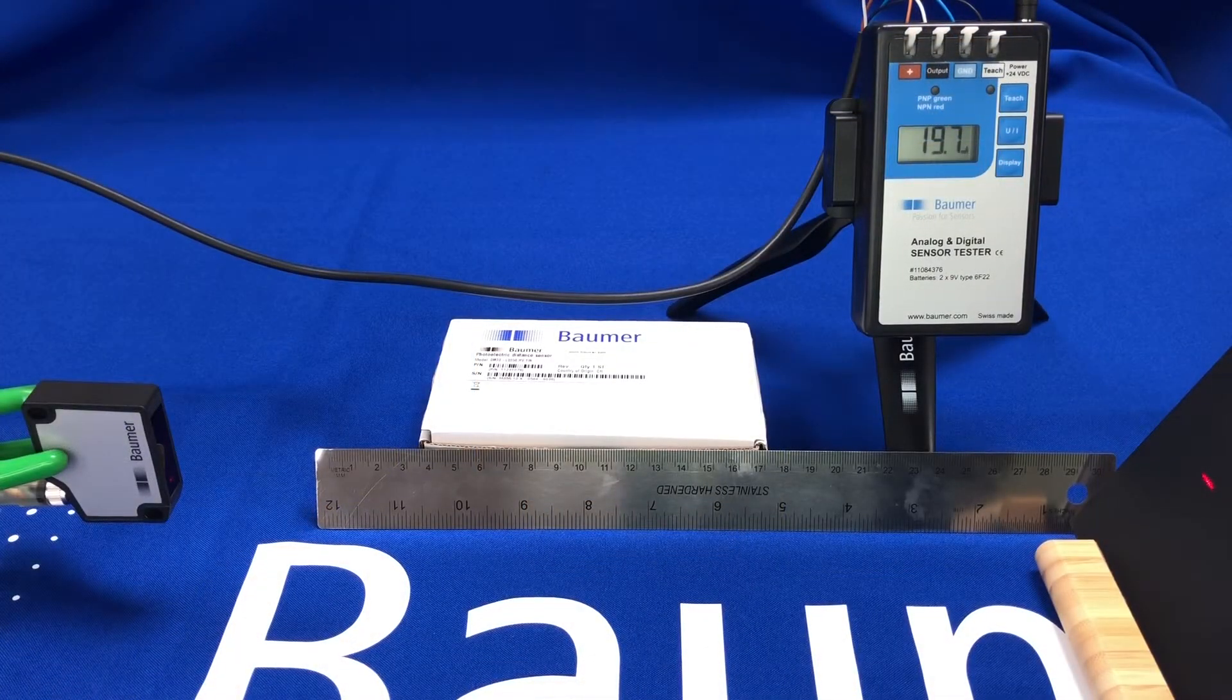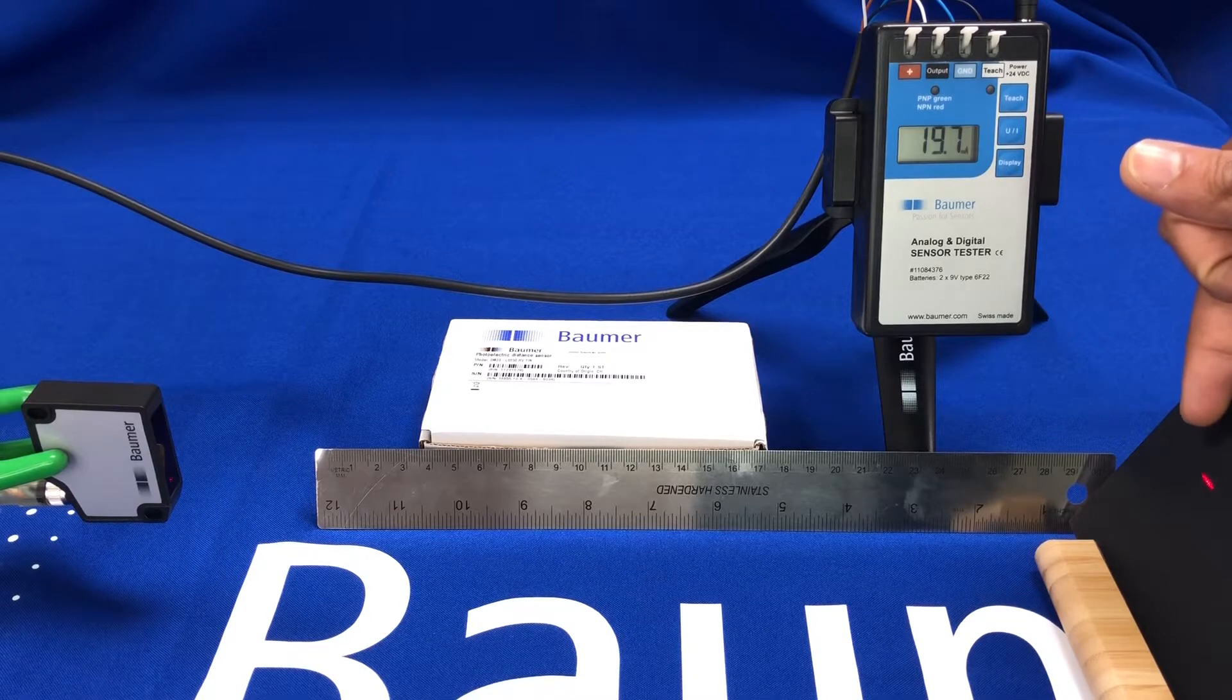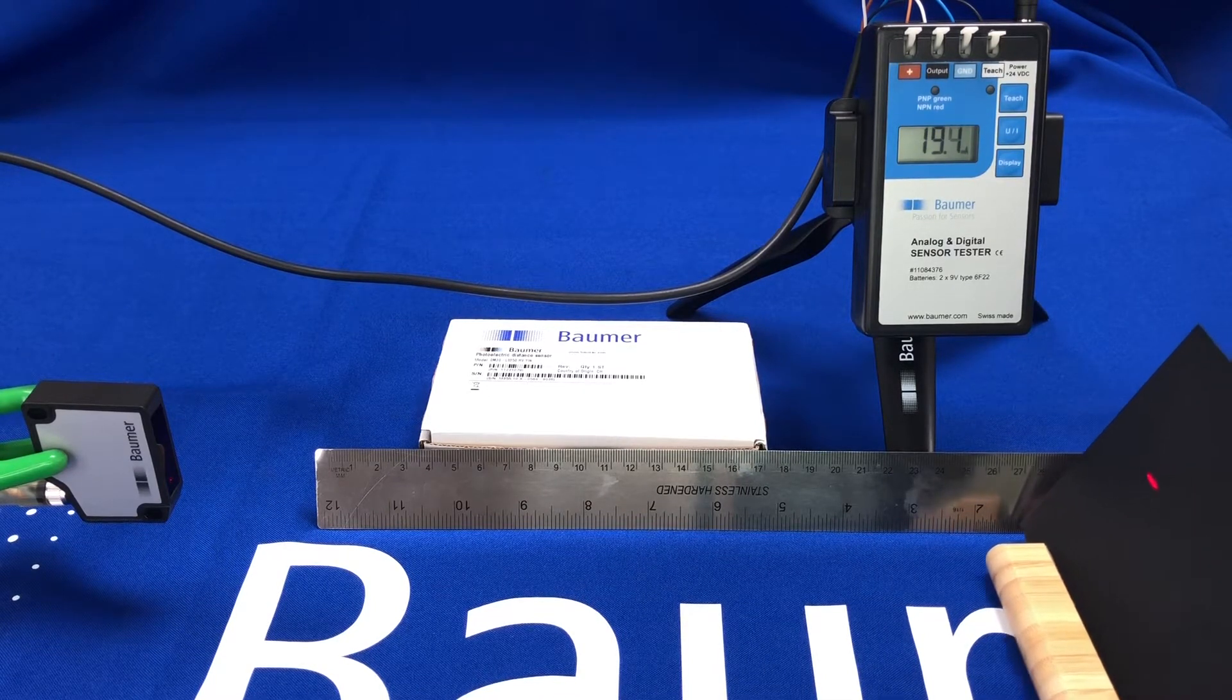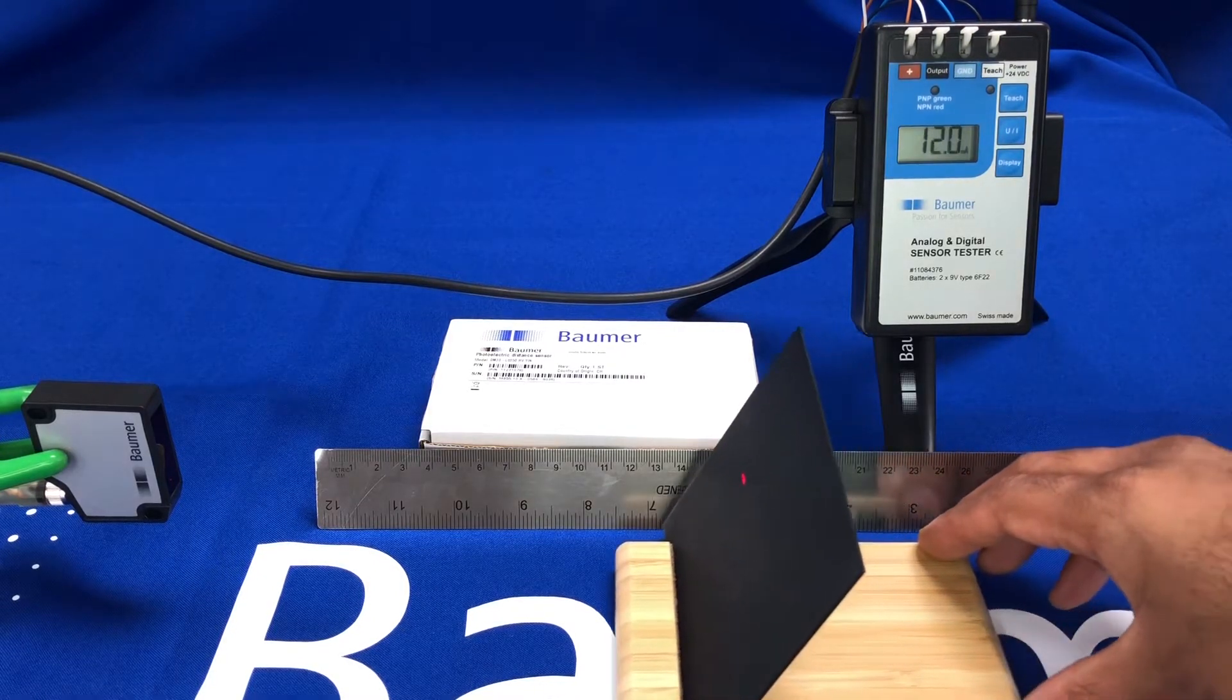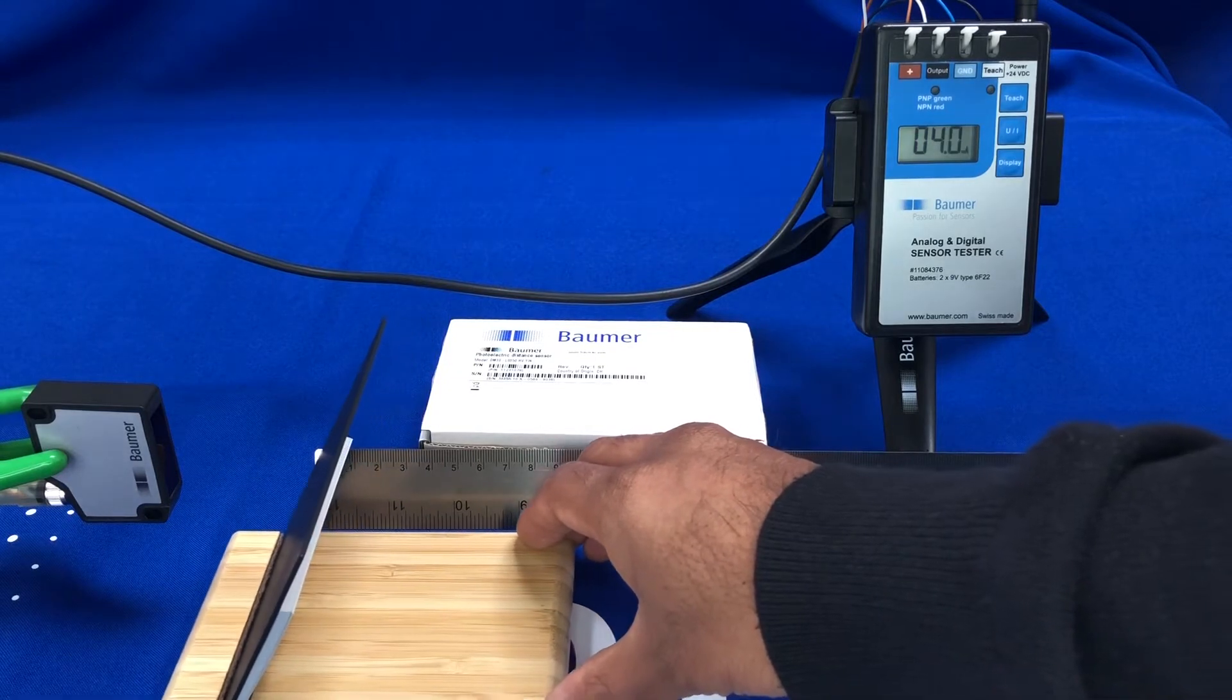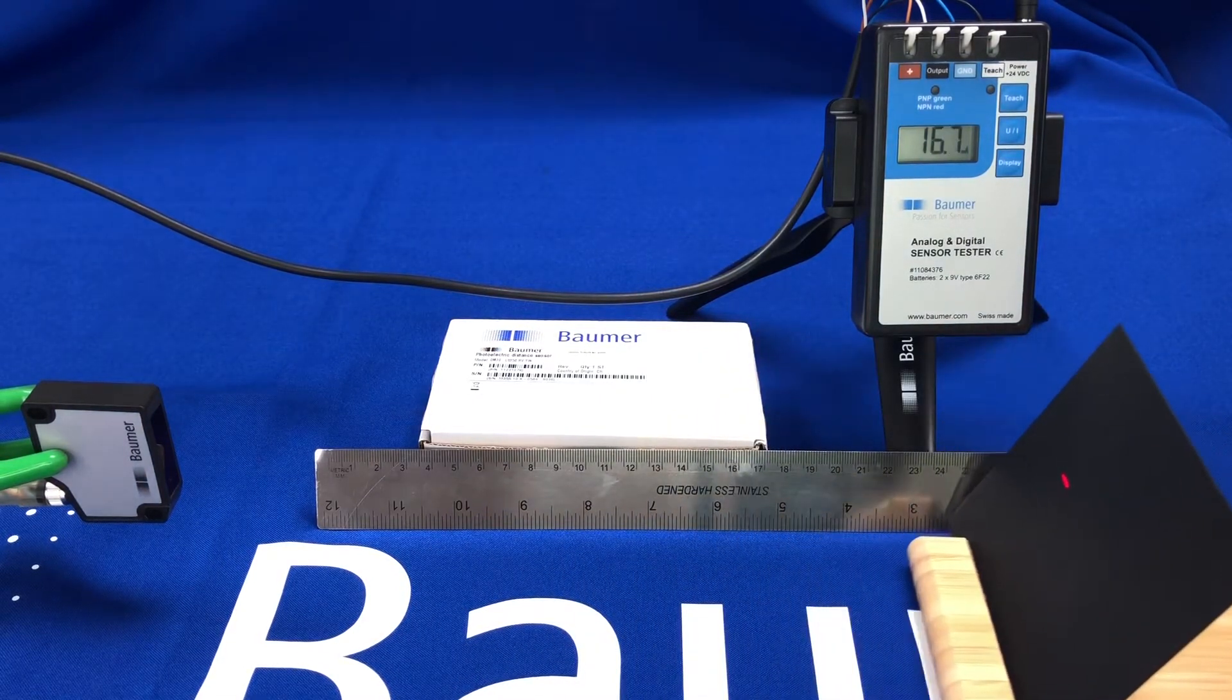Just to show the analog output over the 300 millimeter sensing range with a dark target. I have my dark target here at 350 millimeters away from the sensor. You can see we've got roughly 20 milliamps there. If I start to index in, you see you get a nice smooth signal all the way down to the dead zone of 50 millimeters, and then back again the other way, a nice smooth signal.